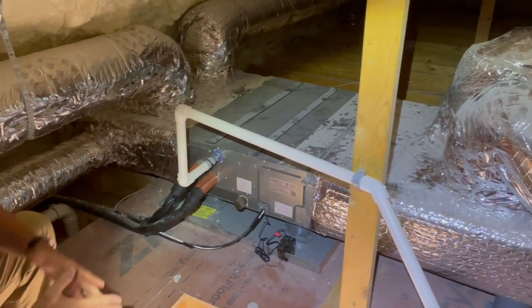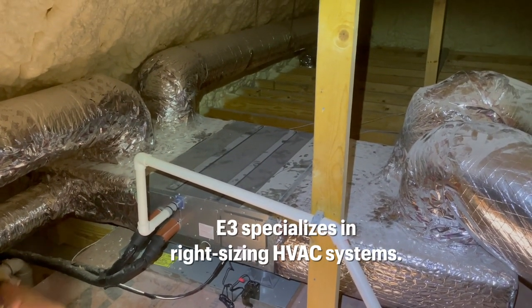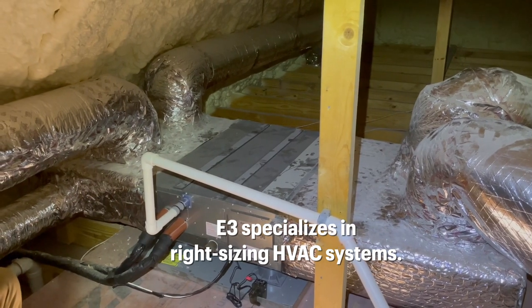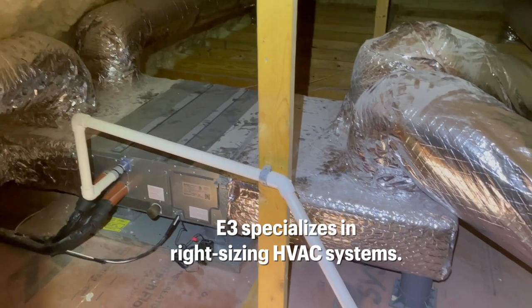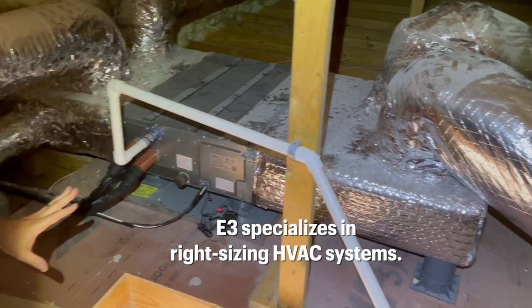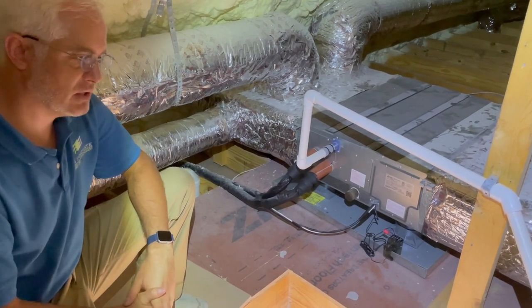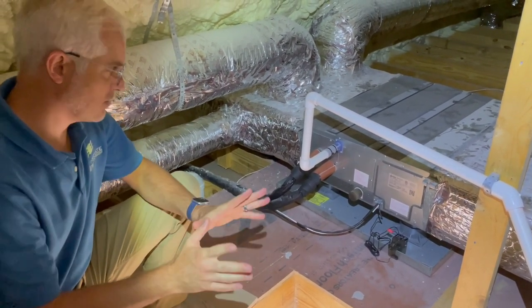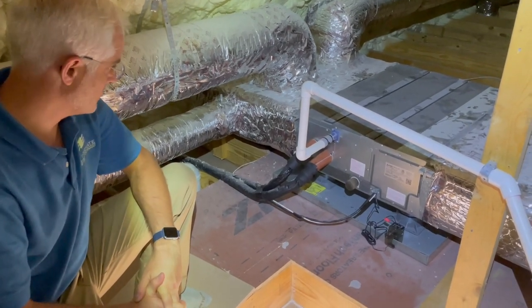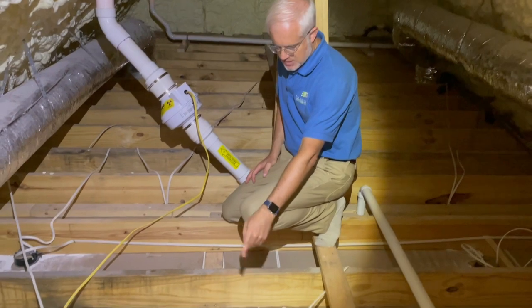This is a very comfortable space up here in the attic. This is a very small, petite air handler — not a big bulky unit like you traditionally see. It's about the size of a large suitcase, and it's providing all the heating and cooling for the third level of the home. Because we've sealed and insulated really well and done the calculations and design work accurately, we're able to serve the needs with a much smaller system.